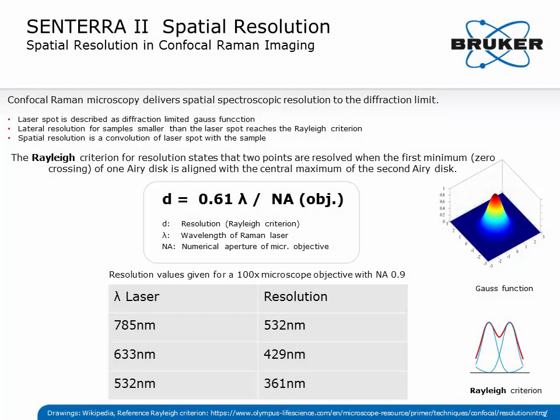The spatial resolution is mainly defined by the Rayleigh Criterion. It states that the resolution is given by 0.61 times the incident wavelength of the Raman laser divided by the numerical aperture of the microscope objective.